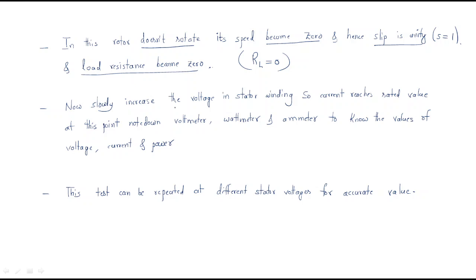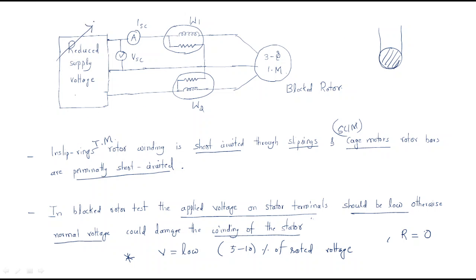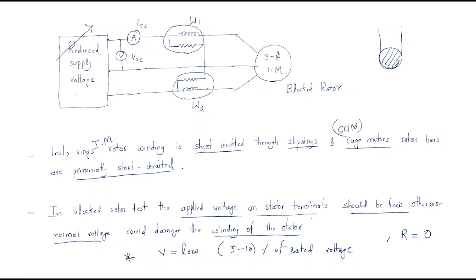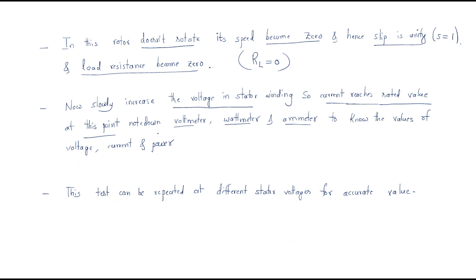In this process, slowly increase the stator voltage — this is in our control. The current reaches the rated value as voltage is slowly increased. At this point, note down the voltmeter, ammeter, and watt meter readings. By slowly increasing the voltage, we record voltmeter, ammeter, and watt meter values.